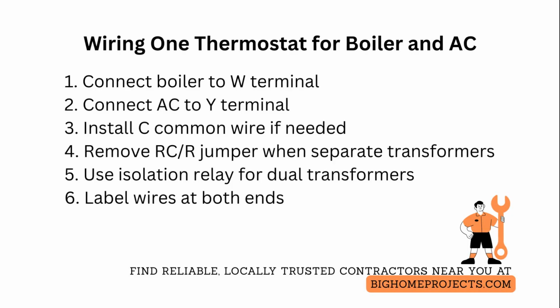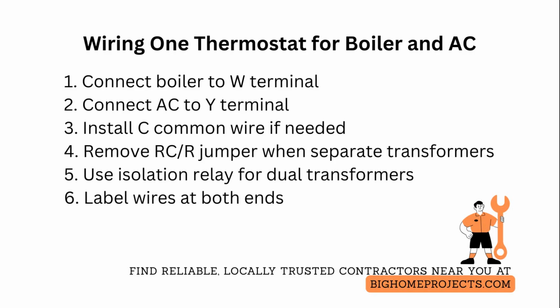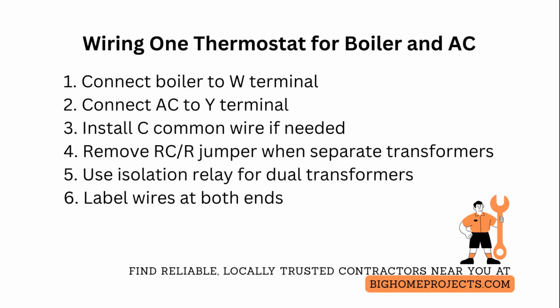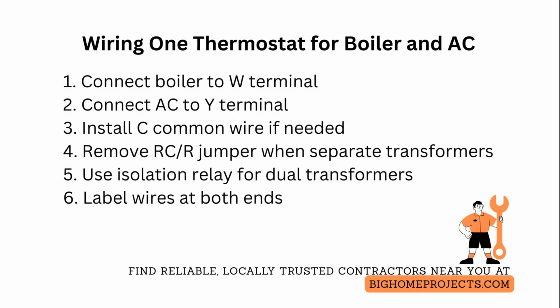Label all wires at both the thermostat and equipment ends with durable heat shrink labels and map each conductor to a wiring diagram. White for heat, yellow for cooling, green for fan, red for 24 volt hot, and blue or black for common when used as C. If an extra conductor is missing, run one new conductor rather than using wire sharing hacks.